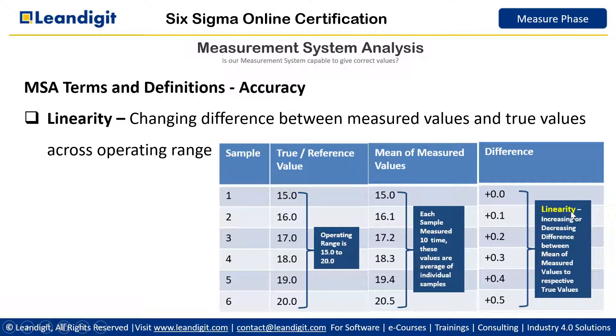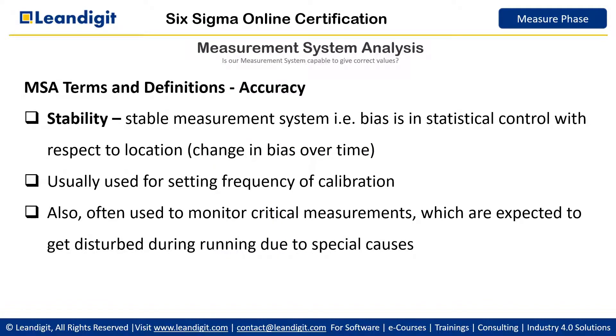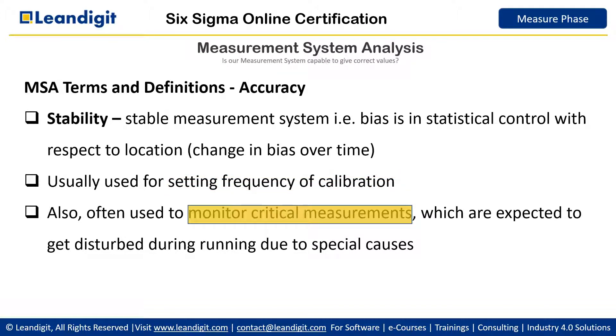Linearity is changing bias across the operating range. Stability is measuring bias over a period of time, and if this bias is in statistical control, we say the measuring instrument is stable. We usually track it over time, and one key objective of a stability study is to set the frequency of calibration. Another reason for doing a stability study is that some critical monitoring instruments can get disturbed during operation and therefore need to be tracked on a regular basis.